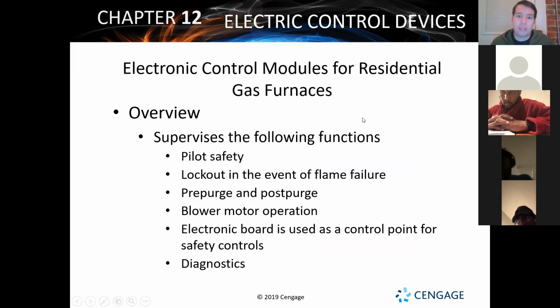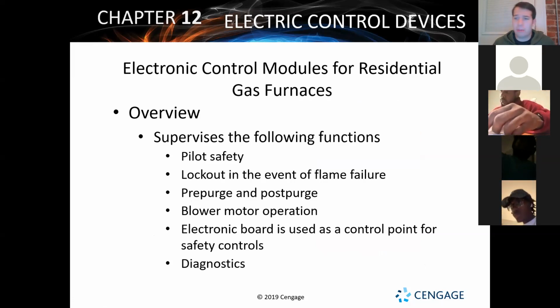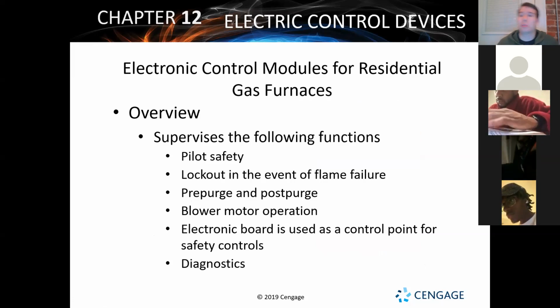So gas furnaces, we'll talk about in a little bit. They've got a lot of different safeties for them. There's a lot of controls and modules. Typically, it's called an IFC, an integrated furnace control, or an IFC board, integrated furnace control board. And that's what you're going to see a lot of times for a gas furnace as far as what kind of control board it's going to have inside of it. And it's going to be operating and controlling a lot of different factors.